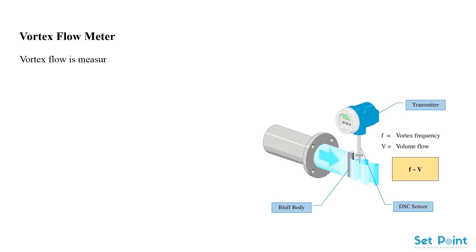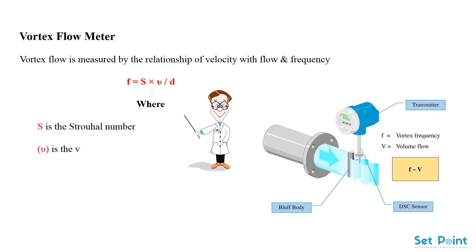Vortex flow is measured by the relationship of velocity with flow and frequency. F equals S multiplied by V divided by D, where S is the Strouhal number, V is the velocity of the fluid, D is the width of the shedder, and RE is the Reynolds number.